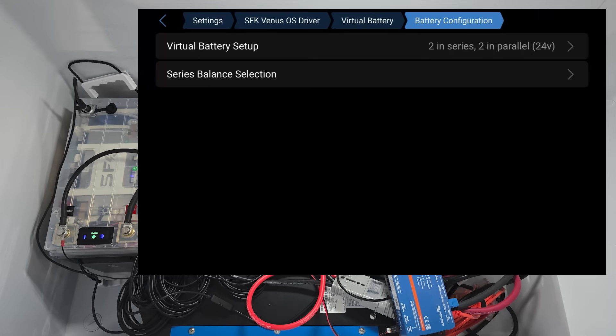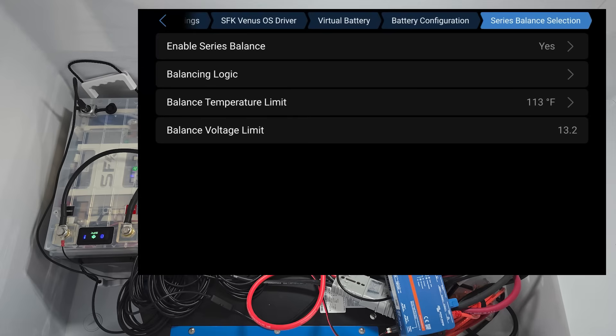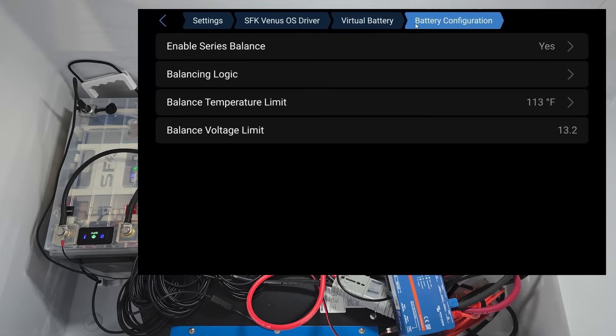This basically tells the Cerbo or the Venus OS how we have our batteries configured. So in this case, we have two in series, two in parallel for 24 volt, 630. We also have series balancing so that even though our batteries are in series, they stay balanced. You can discharge any battery that's higher so that it always is equal with the rest. And that's something that we can set up and this battery is configured to keep balance in series. If you want to learn more, we've got some videos explaining that. You can check that out.